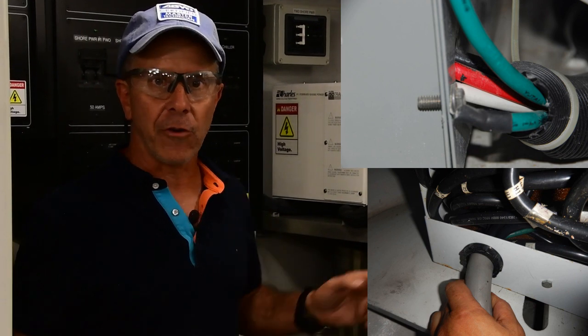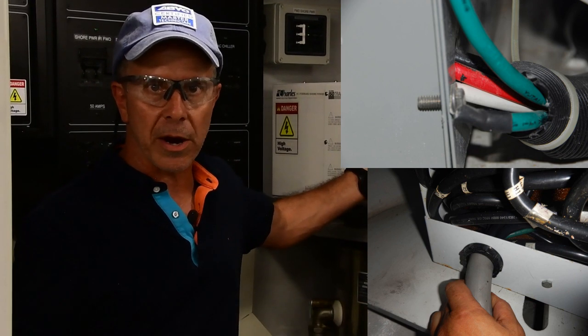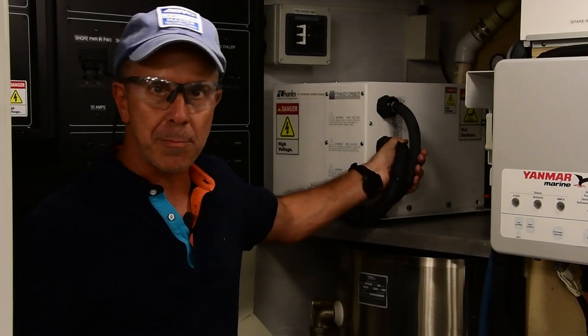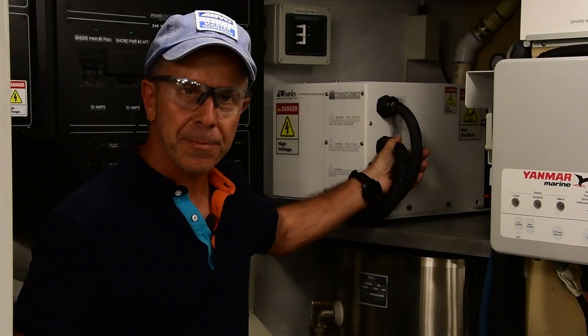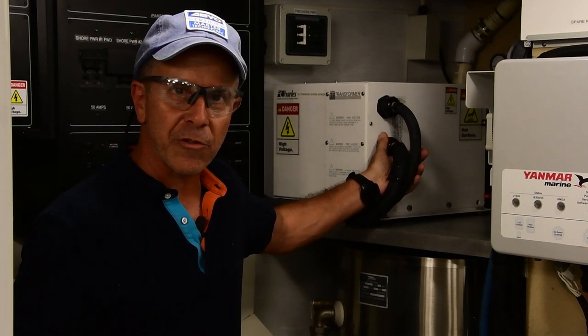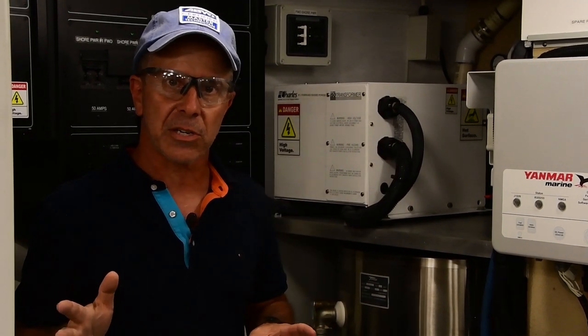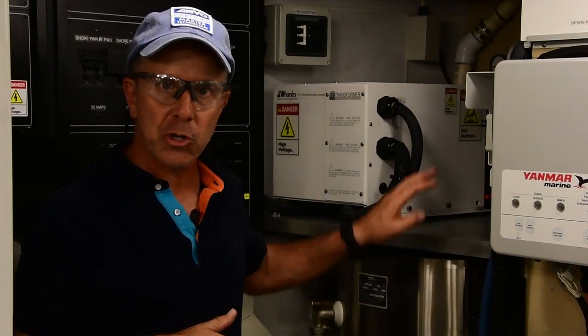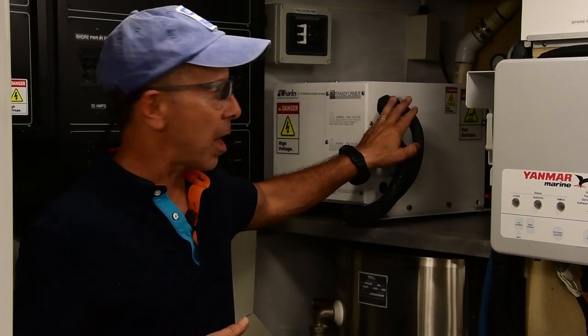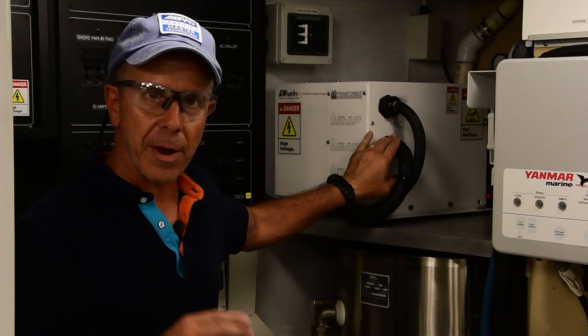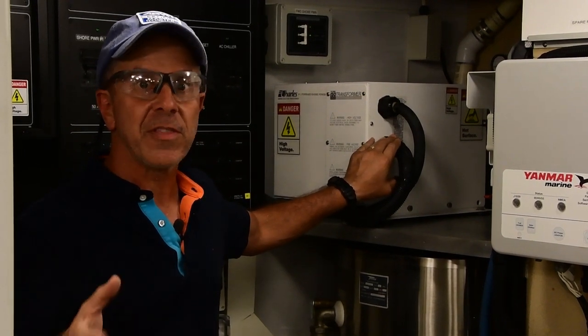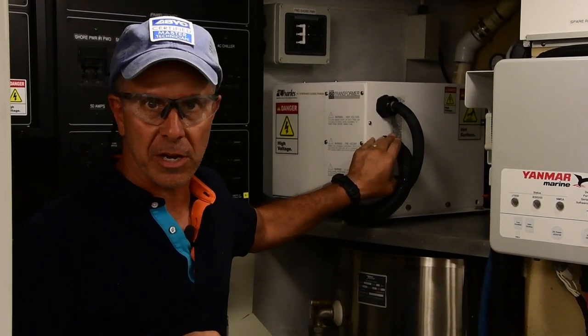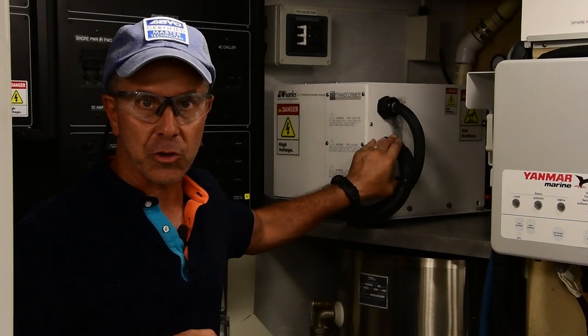You need to have full immobility of these wires so that they're not pulling on the connections inside the transformer. If I can move these wires in and out of however they're passing through the transformer, they've failed that test for the need for a cord grip. So make sure your installation fully complies and utilizes a cord grip that protects the wires from chafe as well as putting strain on the connections inside the transformer.